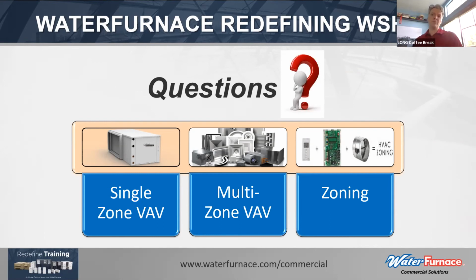I think you answered one of my questions, Rich, to start off, about BAS interface. You said in the last few slides that is certainly available in these systems, correct? Yes, that is correct. It is only available in BACnet. Unfortunately, LON seems to be a disappearing communication protocol for many controls companies. And so we don't have the ability to do anything other than Open N2 or BACnet at this point. Yeah, and BACnet is typically what we see requested in specifications, so I don't see that as a big concern these days. But about size and configuration, what size do these units come in, and can we get them in vertical and horizontal styles? Sure.